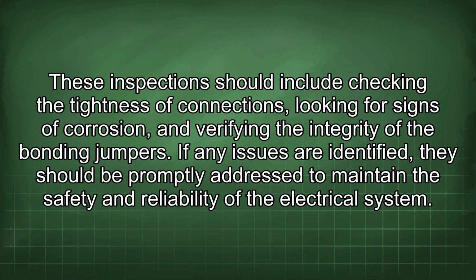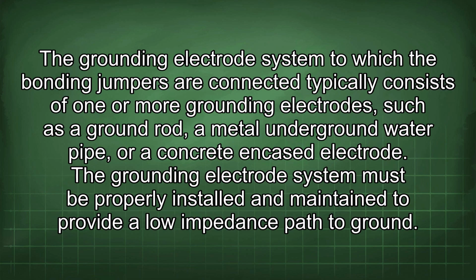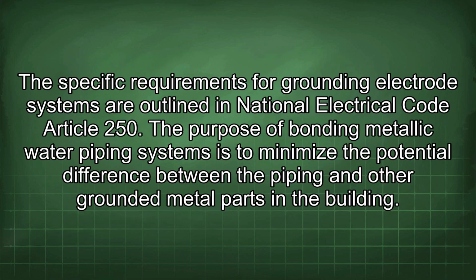The grounding electrode system to which the bonding jumpers are connected typically consists of one or more grounding electrodes, such as a ground rod, a metal underground water pipe, or a concrete encased electrode. The grounding electrode system must be properly installed and maintained to provide a low impedance path to ground. The specific requirements for grounding electrode systems are outlined in National Electrical Code Article 250.